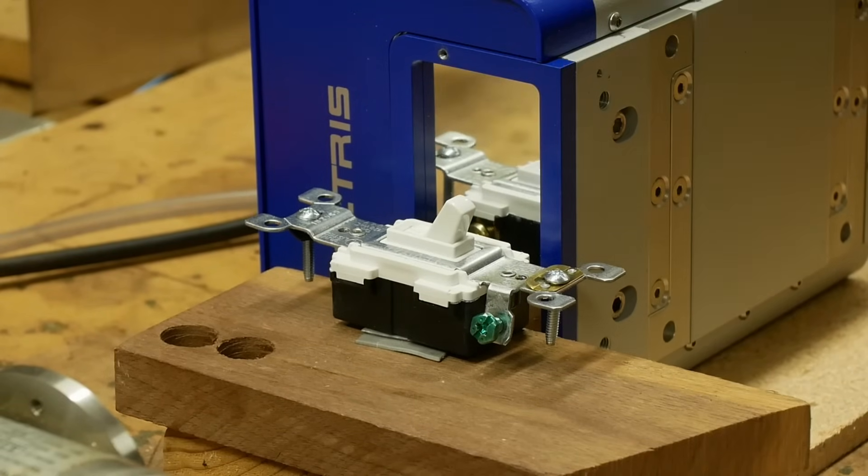In this case, I turned the frame rate back down to about 60 frames a second because getting enough x-rays even through this plain old switch was a problem.